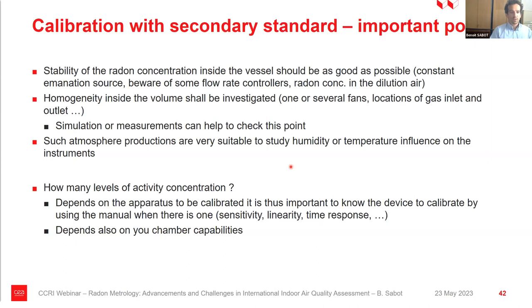What is more interesting in such a setup compared to the primary calibration is that here you will be able to produce a radon atmosphere with many different humidity and temperature conditions, and study a lot of different kinds of influences on the measurement. So it's, let's say, the most useful way to produce a radon atmosphere and to study many effects on your detector system or on materials and so on.